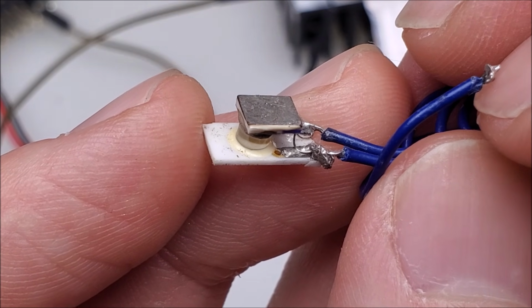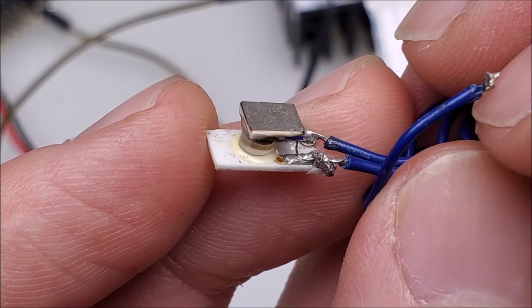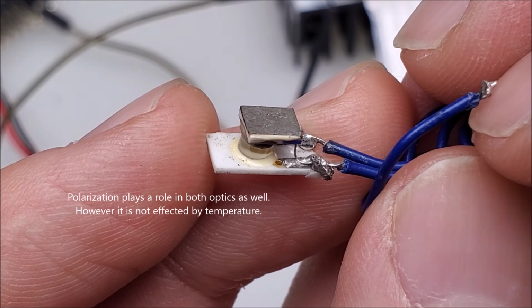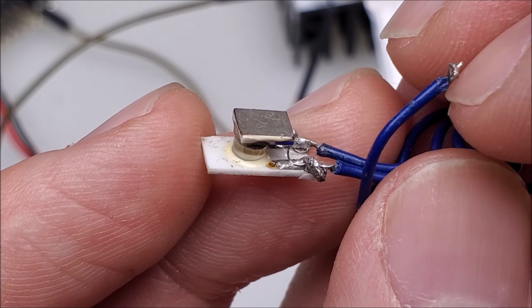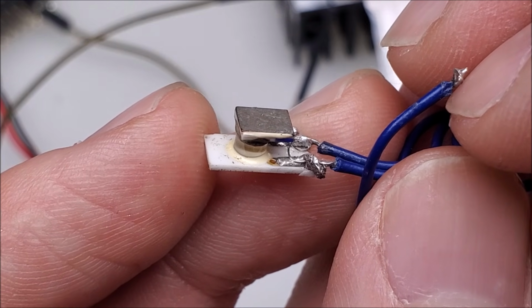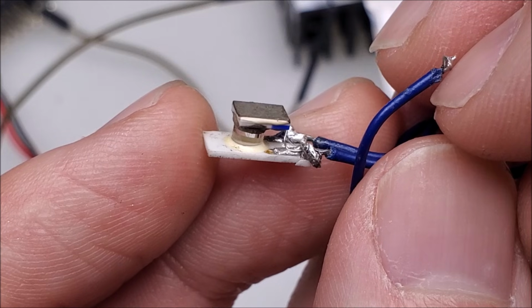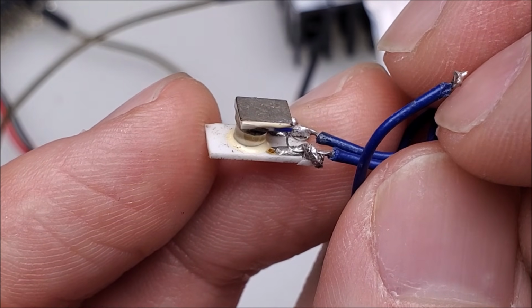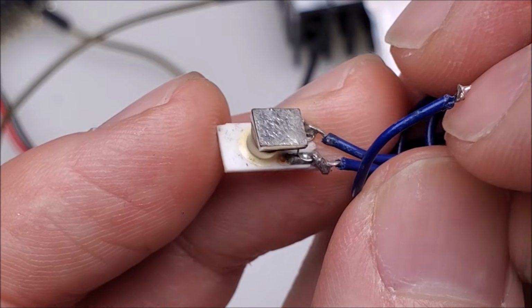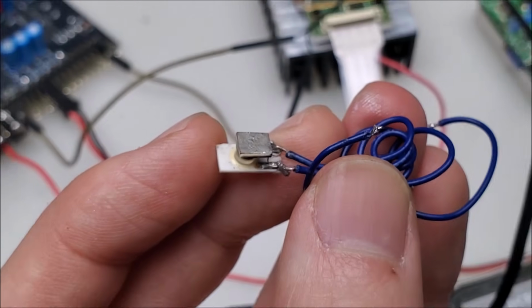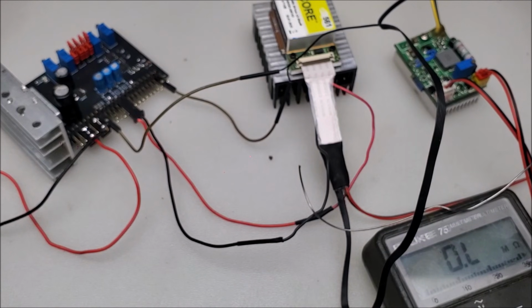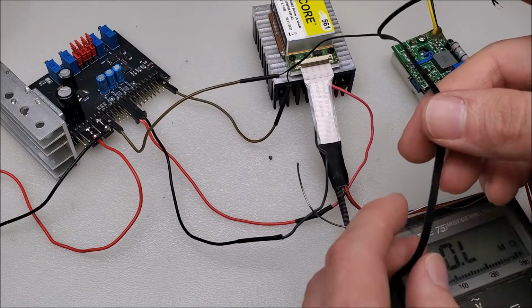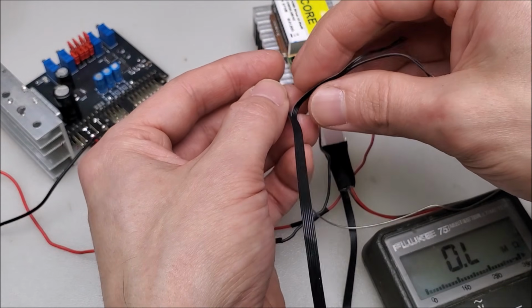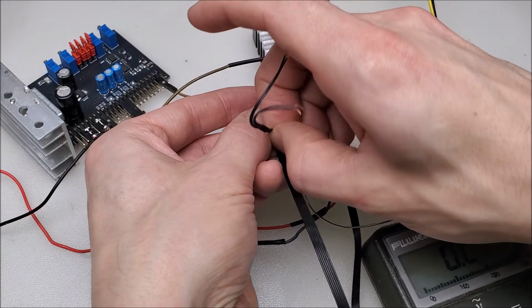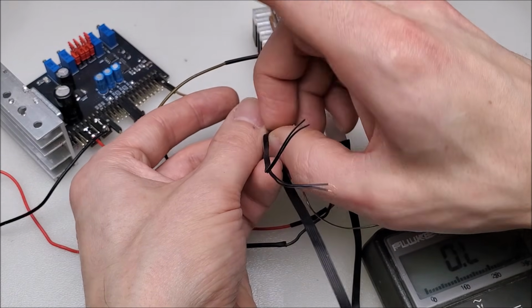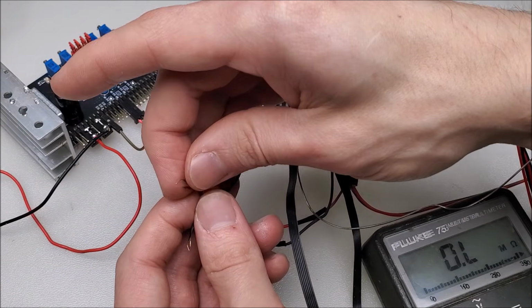And the reason why they need to be kept at a specific temperature is that the birefringent filter works on refraction, and refraction changes ever so slightly with temperature. So basically the birefringent filter is just a narrow band filter which cleans up the light coming from the OPS chip and makes sure that it's very narrow band. So that's one thing. And then the second harmonic generation crystal needs to be held at a specific temperature so that it can do the phase matching correctly in the crystal. That's non-critical phase matching. You can go ahead and look it up. I talked a little bit about that in the last video as well.